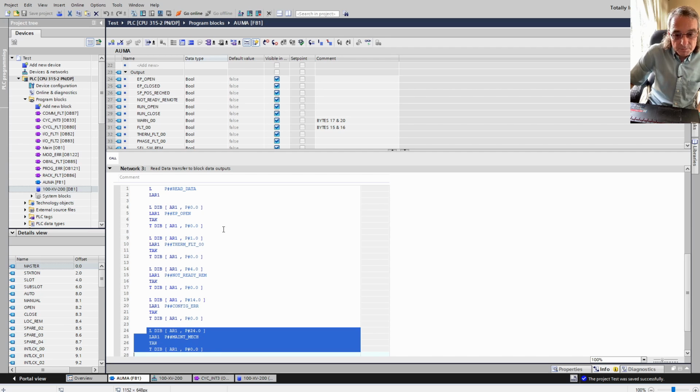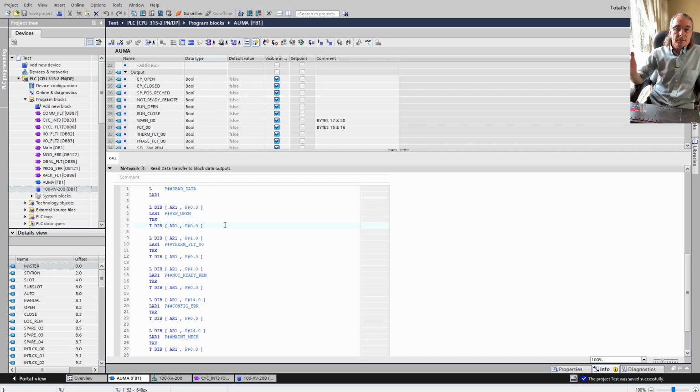With a very minimal bit of code, we've got 40 signals, and as long as we keep our block interface consistent, we can add 7 bits before this, we can add 7 bits in it, as long as we don't interfere with the byte that's there. So we can add another byte anywhere in this, and our code, we don't have to go and change. And that's what we really try.